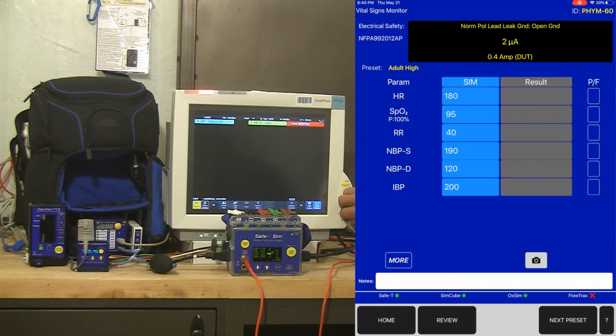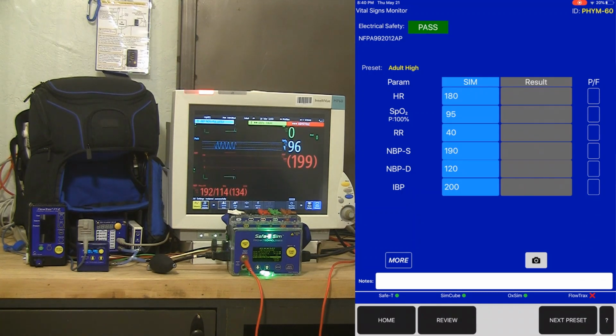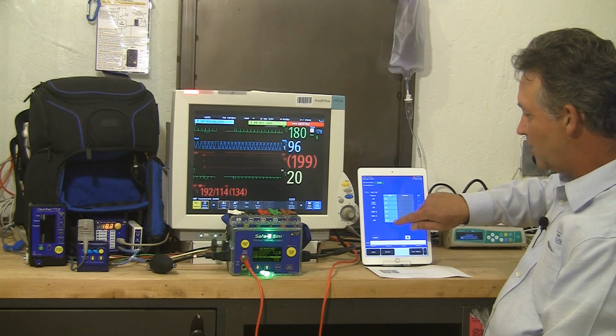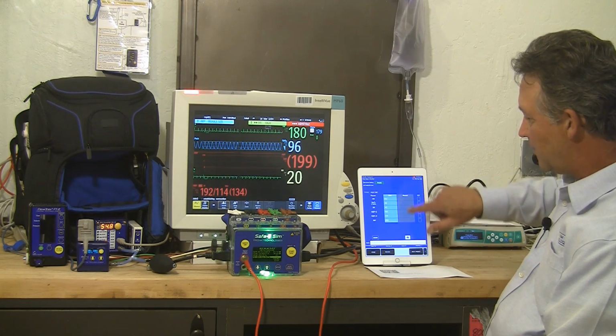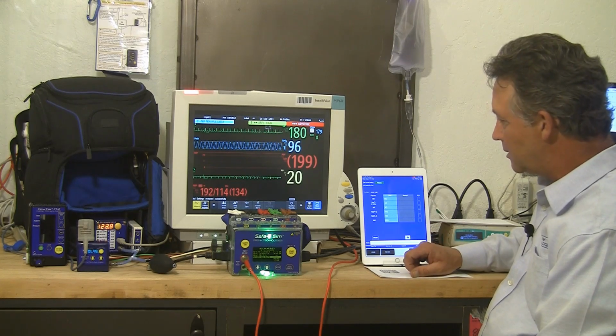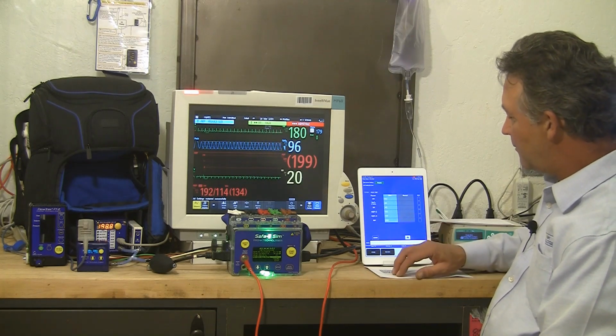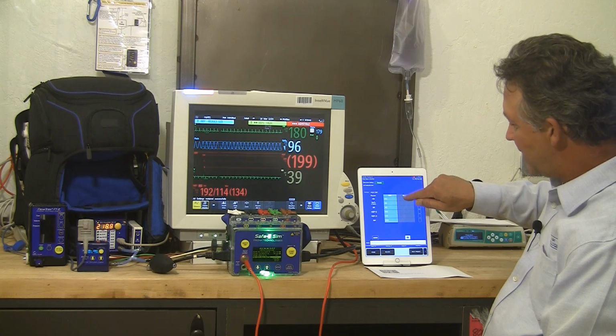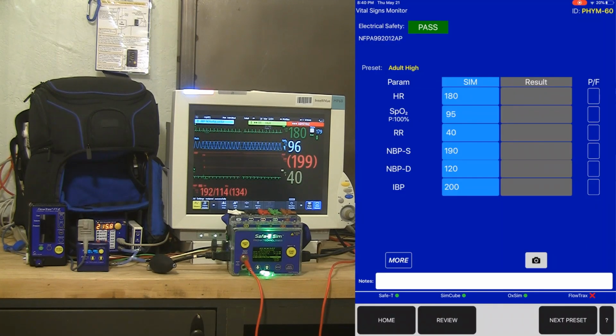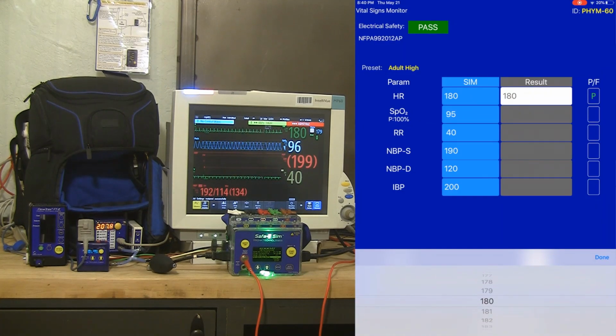As soon as the monitor powers up, I've got a pass for electrical safety already, and I can hit start on the NIBP. On the left-hand side of this screen, you'll see the simulated values. On the right side is where you can populate the results. I'm starting the NIBP right away because while that's taking a measurement, I can tap on the results box and capture my heart rate result.